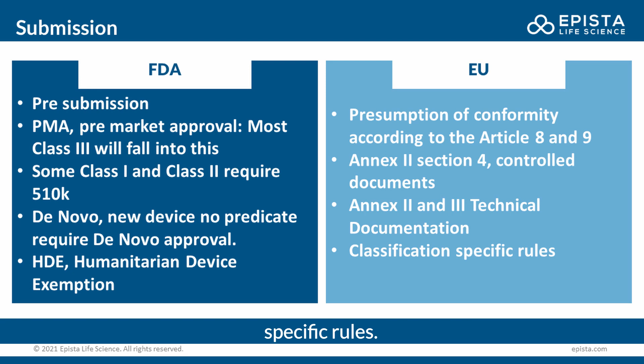If we think of where to go from here with my product, I think the key question to solve would be: could it be class 1? And probably it will not be a class 1 product if the pyramid has been turned upside down. I think it is very important for manufacturers to start early and get your quality management system certified and approved pronto, very quickly. Also involve the notified body early in the process, do a good pre-study, search for existing products, and remember what you just said: the approval route and the submission fully depend on the product risk and the classification information. So it's a sum of three different factors.